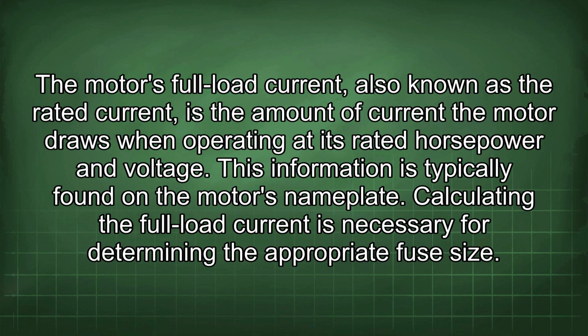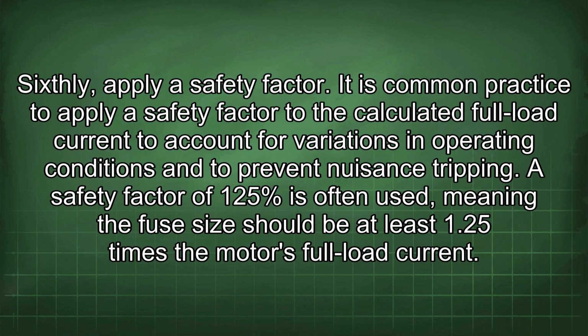This information is typically found on the motor's nameplate. Calculating the full load current is necessary for determining the appropriate fuse size. Sixthly, apply a safety factor. It is common practice to apply a safety factor to the calculated full load current to account for variations in operating conditions and to prevent nuisance tripping.